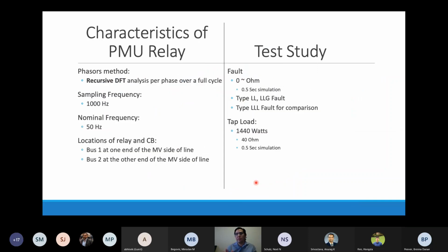So, the characteristics of the system: our phasors were calculated by a recursive DFT over a full cycle. Our sample frequency is 400 Hertz. Our nominal frequency is 50 Hertz. And we are testing at both ends of the line, which we will call, for this example, bus 1 and bus 2. On the medium voltage side of the line, we are testing a fault. We will test all the common faults I presented earlier. Also, we will test a tap load, which means that instead of a fault, we have a tap load connected on this line, to see its response and contrast it, and to show how it doesn't affect the proposed detection method.